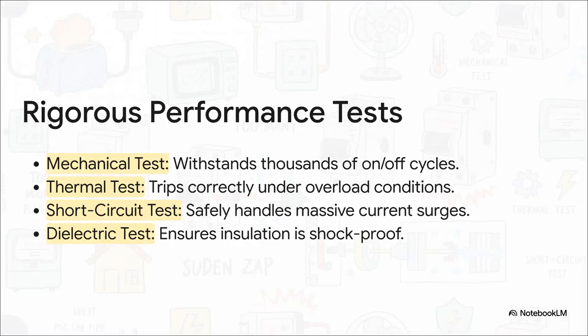And before any MCB ever makes it into a wall, it goes through a brutal series of tests based on strict international standards. They flip it on and off thousands of times. They carefully heat it up to make sure the thermal trip works at the exact right temperature. They hit it with a massive short circuit current to prove it can handle the absolute worst case scenario. Its insulation is even zapped with high voltage to make sure it's safe to touch.